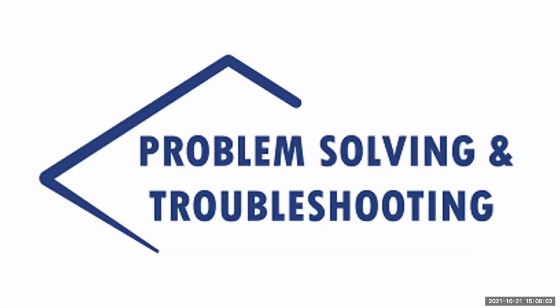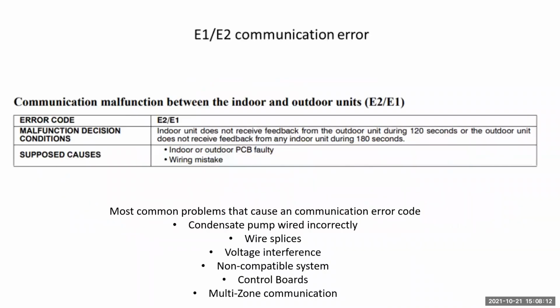However, I'm going to go over some of the most common error codes we have and some of the ways to troubleshoot them. E1, E2, mostly E1 is our most common error code. This includes troubleshooting the wiring, condensate pumps, voltage interference, sometimes control boards.